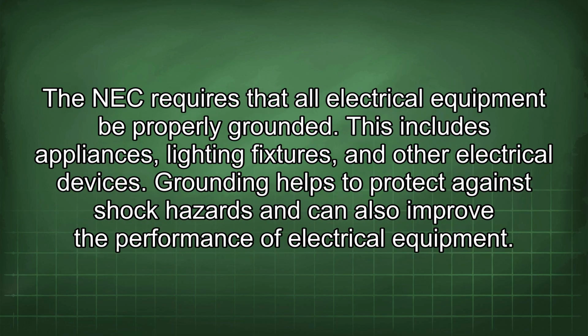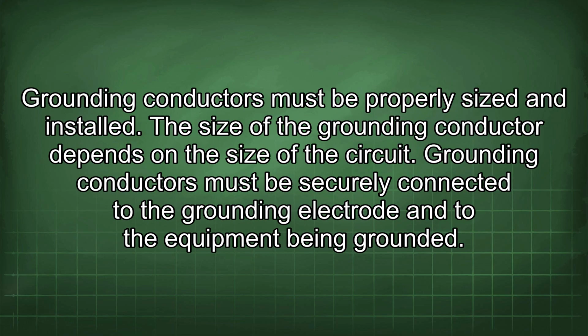The NEC requires that all electrical equipment be properly grounded. This includes appliances, lighting fixtures, and other electrical devices. Grounding helps to protect against shock hazards and can also improve the performance of electrical equipment. Grounding conductors must be properly sized and installed. The size of the grounding conductor depends on the size of the circuit. Grounding conductors must be securely connected to the grounding electrode and to the equipment being grounded.